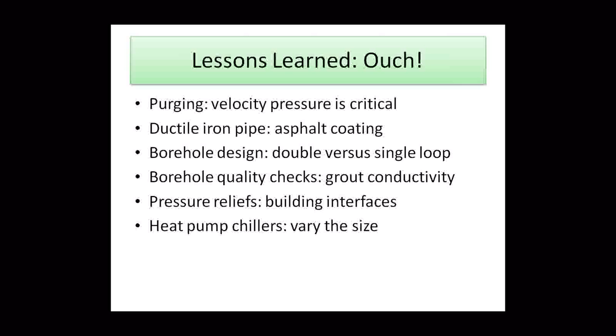If I had to do it over again, instead of 4 heat pump chillers that are 2,500 tons each, I'd probably have one of those 2,500 ton chillers cut in half and have 2 1,250s. It's so efficient, there are times of the year I could get by with one 1,250 ton unit for heating the campus.